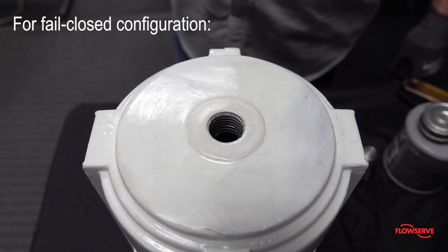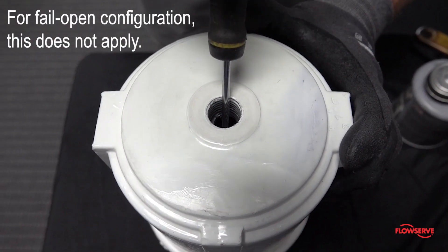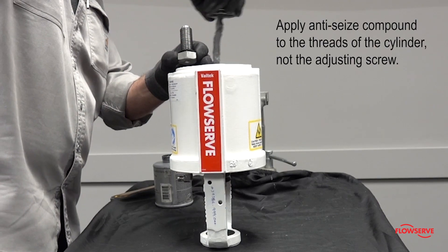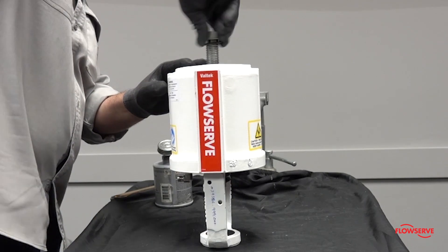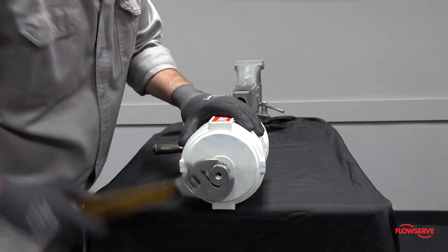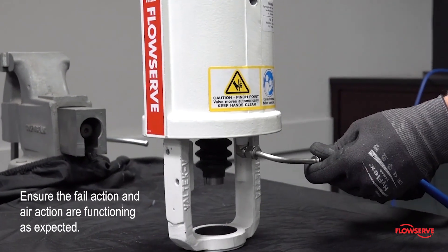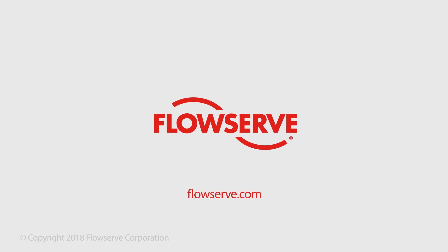For fail closed configuration, make sure that the hole in the spring button is lined up with the hole in the cylinder. This does not apply to fail open configurations. Replace the rubber elastomer gasket and apply anti-seize compound to the threads of the cylinder, not the adjusting screw — this will prevent grease from collecting on top of the cylinder, which can cause the gasket to squeeze out of place. Install the adjusting screw and tighten until the gasket is compressed sufficiently to seal. Stroke the actuator to ensure that the fail action and air action are functioning as expected. For more information about Valtek actuators, visit Flowserve.com or contact your local Flowserve sales representative.